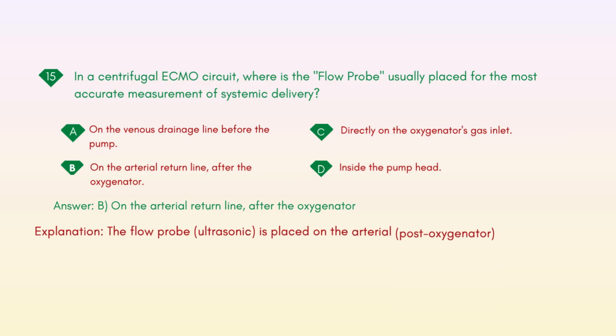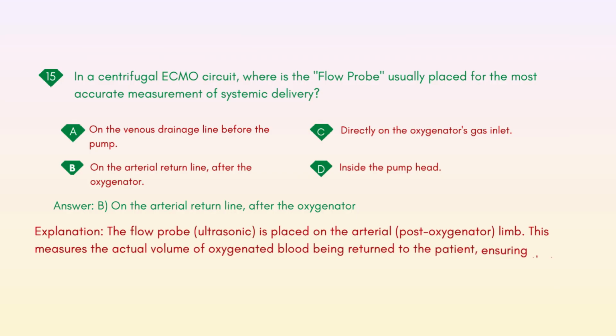Explanation: the flow probe, ultrasonic, is placed on the arterial, post-oxygenator, limb. This measures the actual volume of oxygenated blood being returned to the patient, ensuring that any shunts or recirculation loops are accounted for.